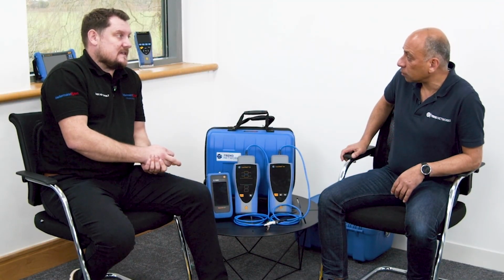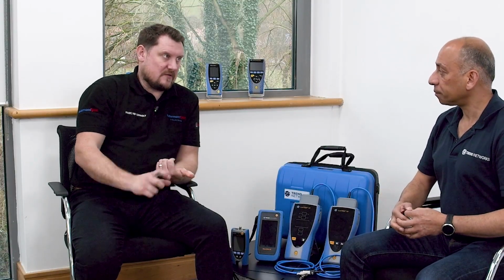And it's to do with the type of containment being used, whether it's basket, perforated, or solid metal, for example. What type of copper Ethernet cabling is being used? Is it Cat6? Is it Cat6A? And obviously they run at very different frequencies, so 250 megahertz for Cat6, 500 megahertz for Cat6A. Cat6A carries a much higher frequency. Whether the cable is shielded or unshielded, and then what the power cabling factor is as well, so actually how many power cabling circuits are running, single phase, 3-phase, what the voltage is - all that sort of stuff. So there's quite a lot to actually consider.